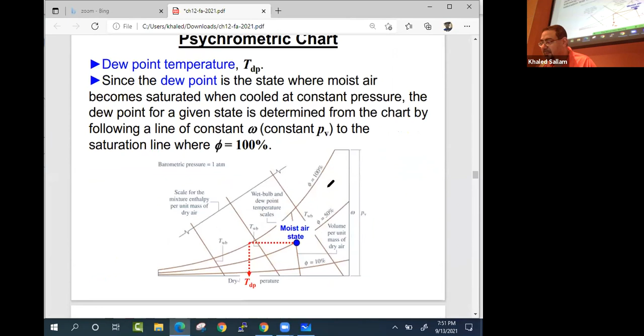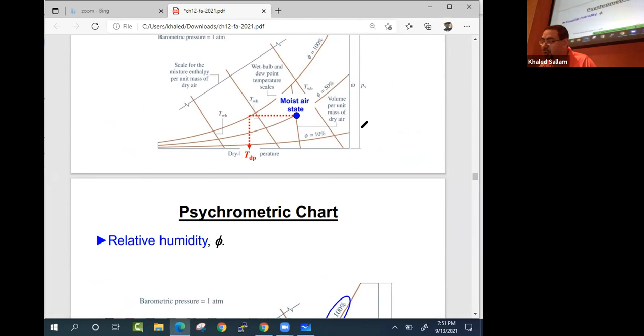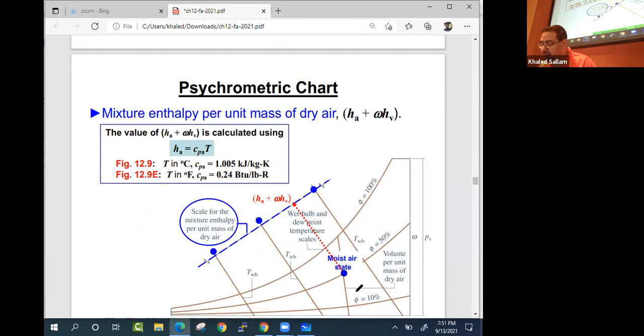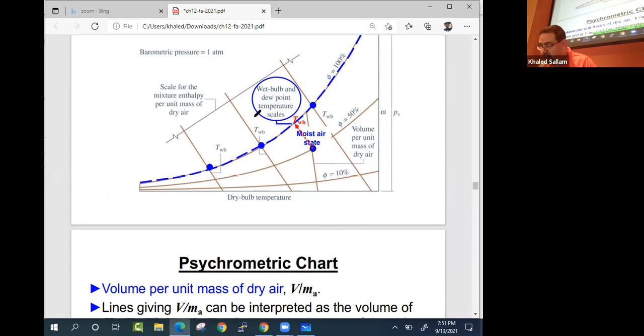He's explaining how you can find your dew point by moving horizontally, how you can find the relative humidity from the curve, how you can find your enthalpy by going up and reading the scale, and the wet bulb temperature by going at constant wet bulb or constant H, which is the same, and reading the temperature on the x-axis. There are also lines here that represent constant specific volume.